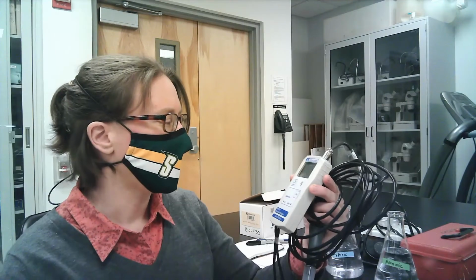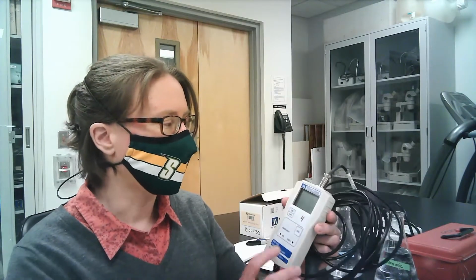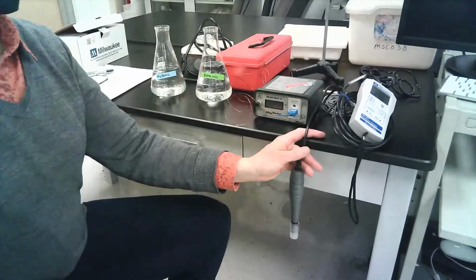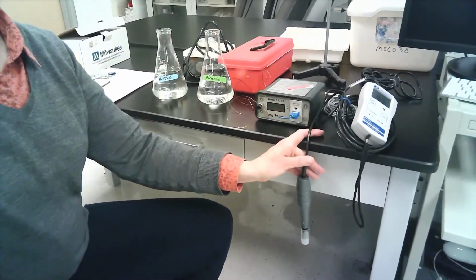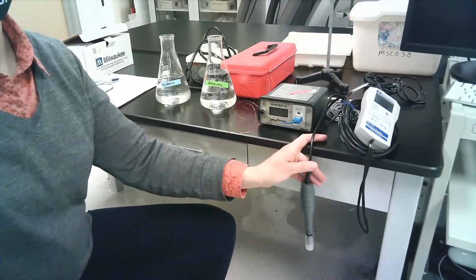This is a dissolved oxygen meter. I've gone ahead and calibrated these units already for you, so you don't need to do any of that. But what I do recommend is these usually work better if they've had a little bit of time to warm up and equilibrate. So when you come in, just make sure that you turn it on, and then while you get it ready, just leave it hanging over the edge of the lab table. That's really the ideal position for it to equilibrate.